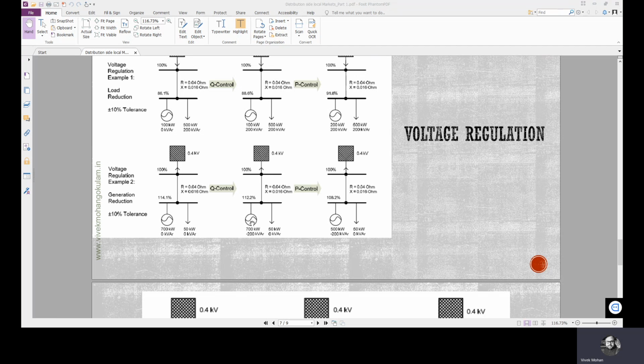That is, if this source has a power electronic interface or an inverter having reactive power control capability, then it can operate in lagging power factor mode, and this 200 kVAR can be consumed from the local node. So because of this, the voltage has been reduced to 112.2%.